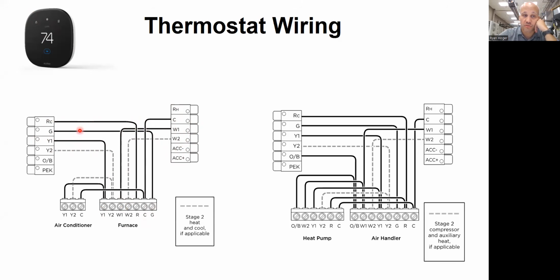So those five wires all go down to the furnace or the air handler, whatever you got. And then two of those wires piggyback outside. And if you have two-stage, then another one as well to your air conditioning unit. When I have a heat pump, it's going to require more wires. This is where the change would come in. When you're replacing an air conditioner with a heat pump, you probably have to run new thermostat wire because you probably don't have enough wires, right?